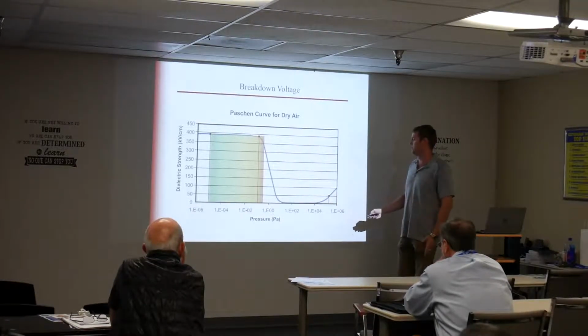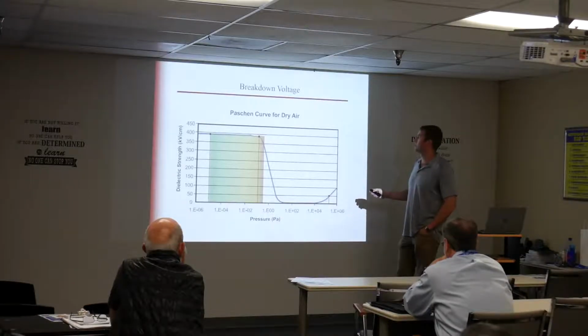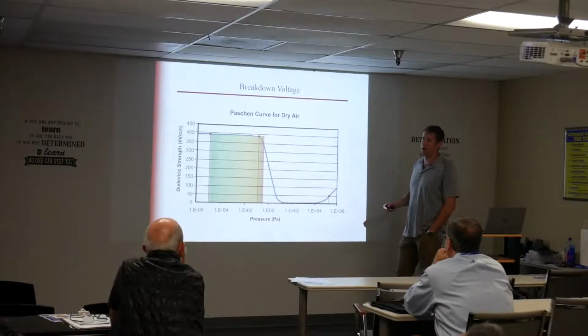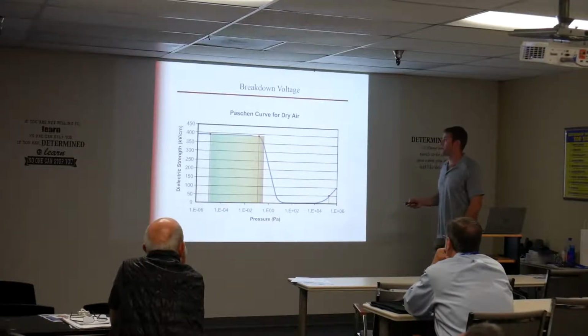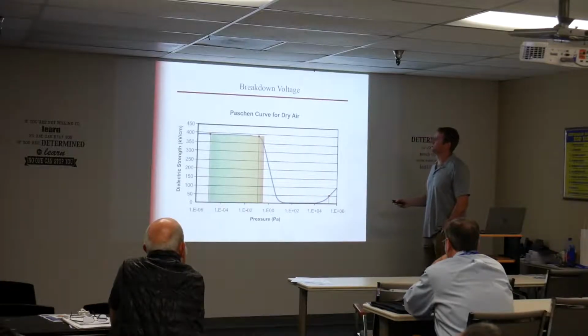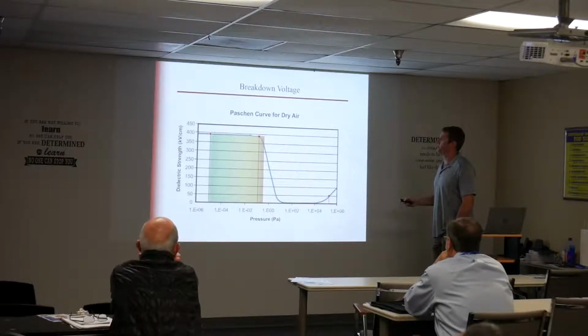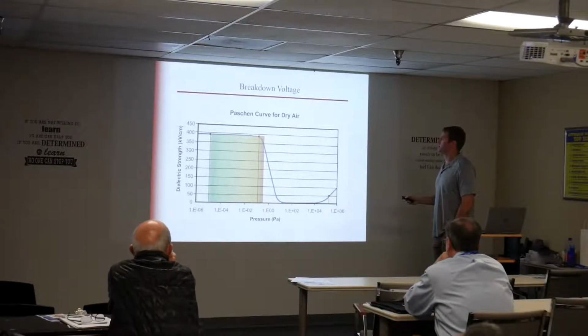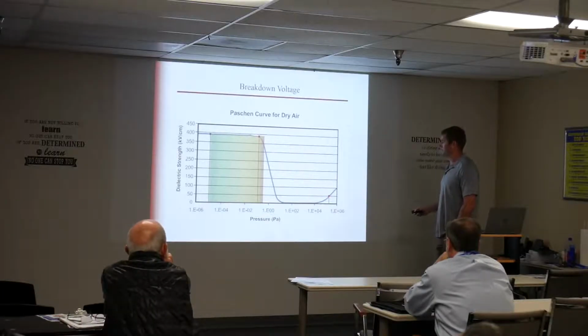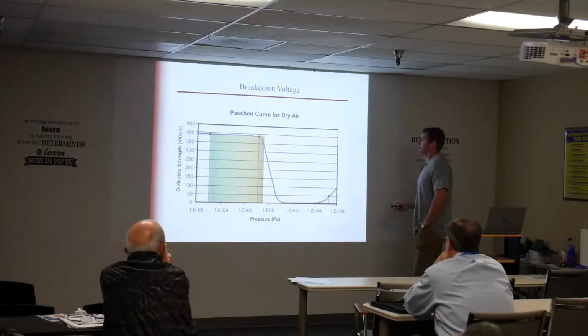It's only 10 millimeters. What it's saying is that with a 10 millimeter contact gap in dry air, it can interrupt 390 kV. That's why vacuum is so popular, so widely used in the power industry. So as you can see, the insulating capability is really, really high. Here it starts to go down. Here's where it drops off. This is atmospheric pressure over here.